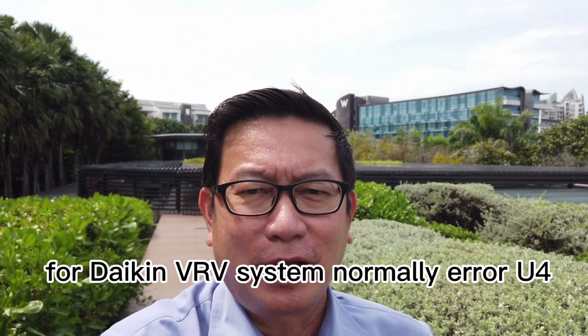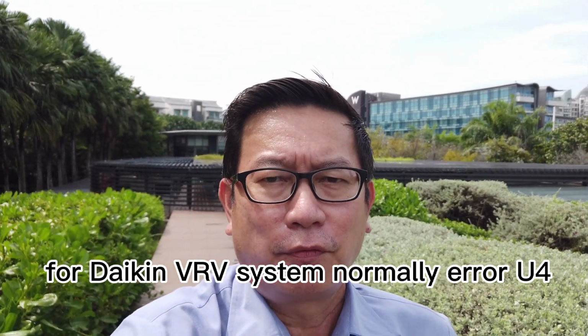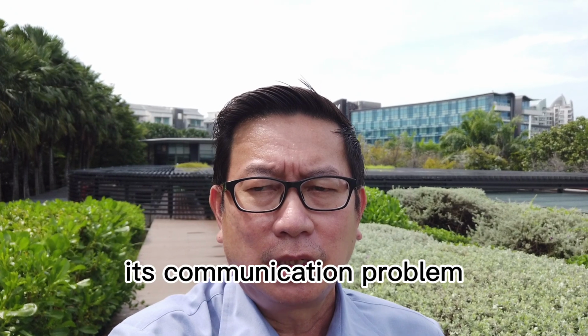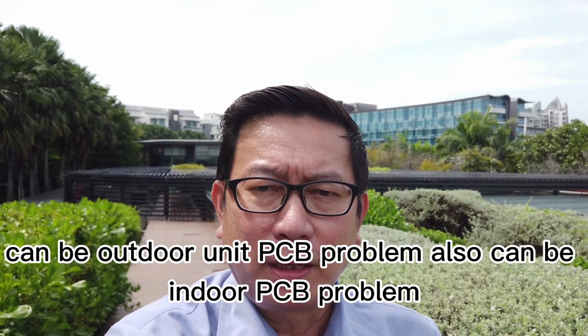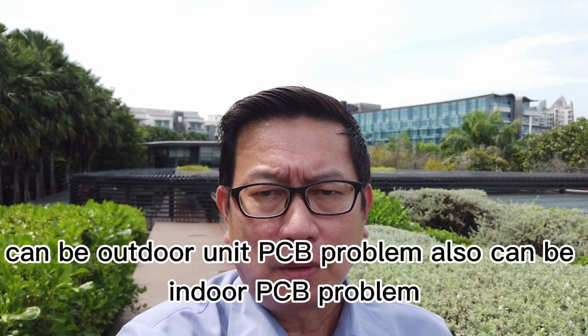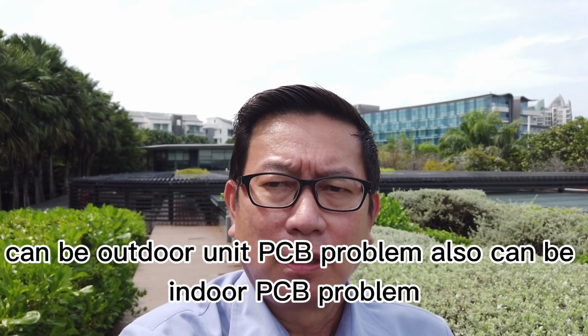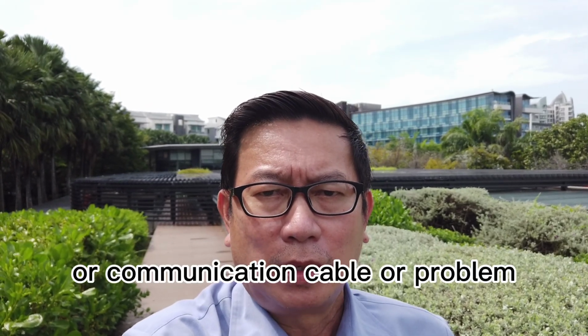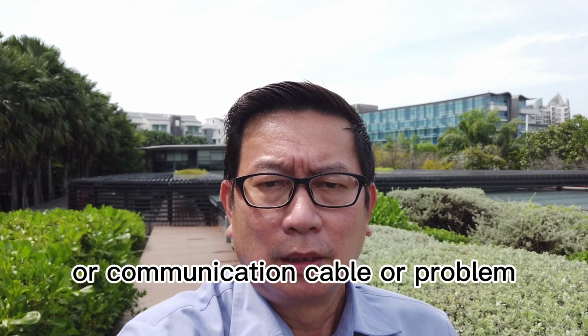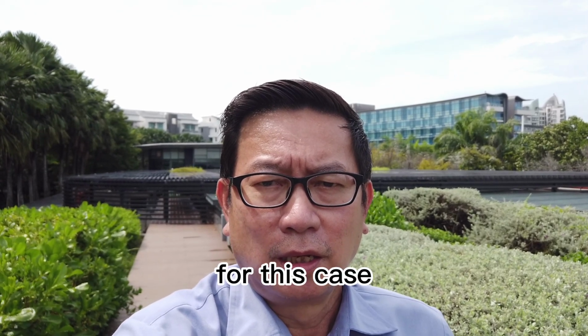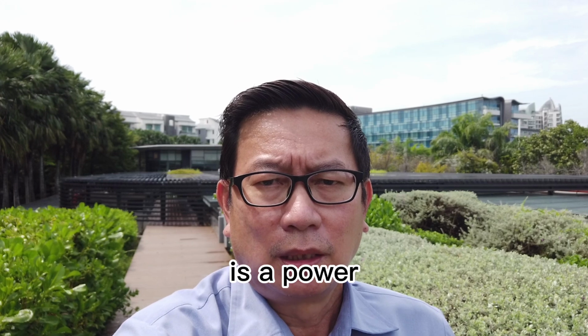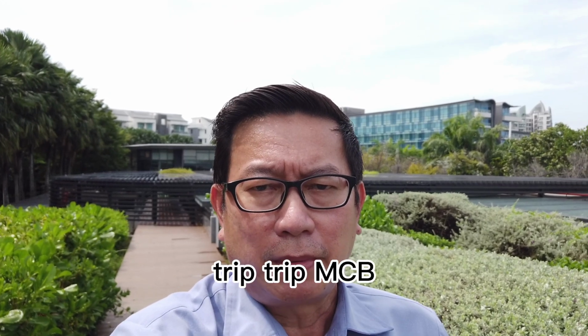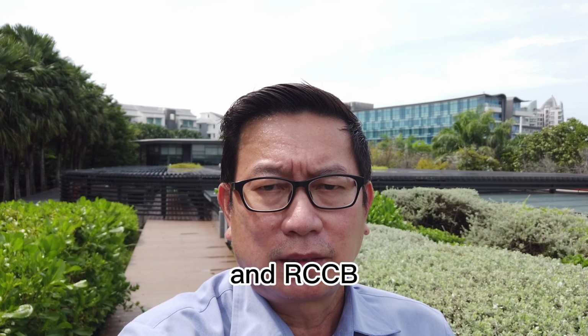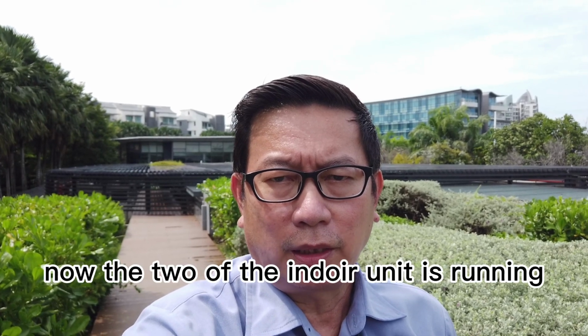For Daikin VRV system, normally error code U4 is a communication problem. It can be an outdoor PCB problem, also can be an indoor PCB problem, or the communication cable got problem. For this case, it's a power trip. Trip MCB and RCCB. After reset the system, now two of the indoor units are running.